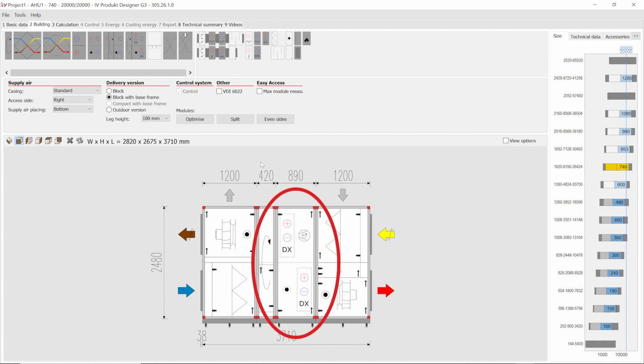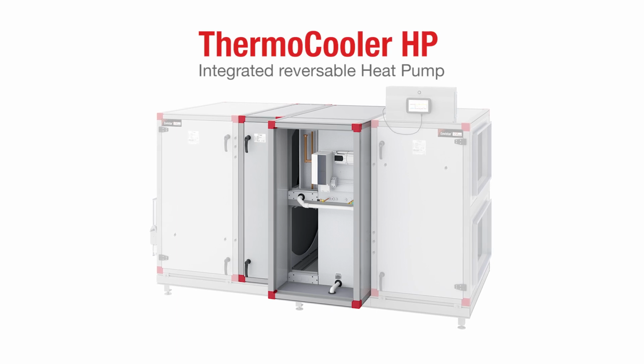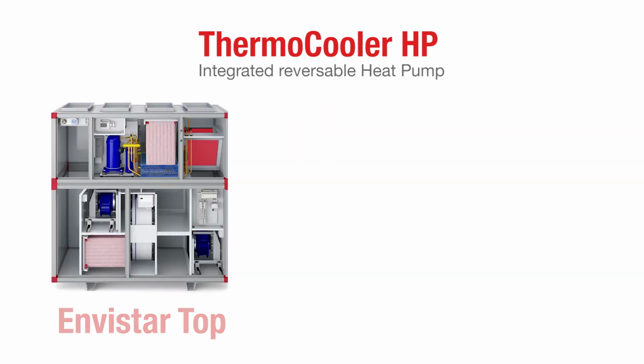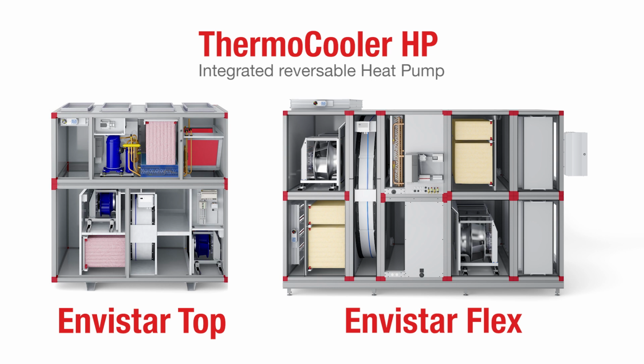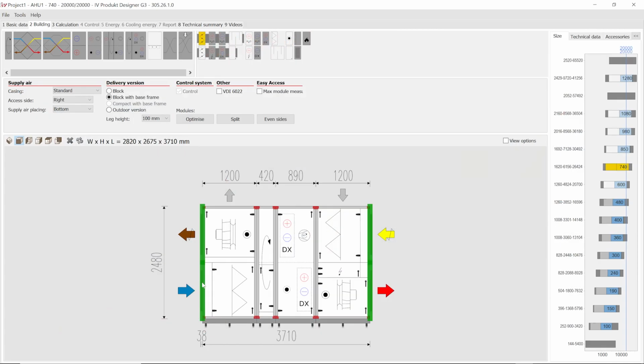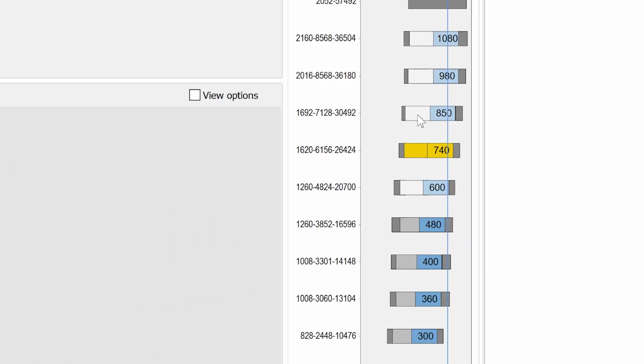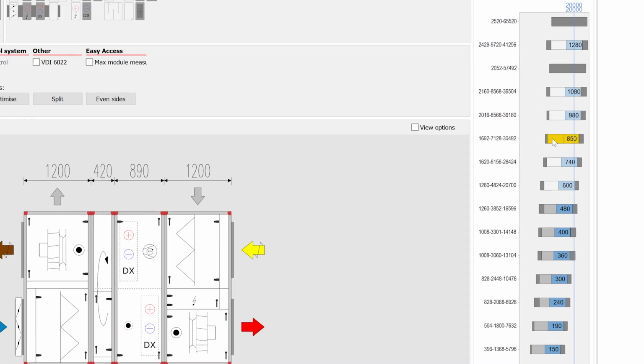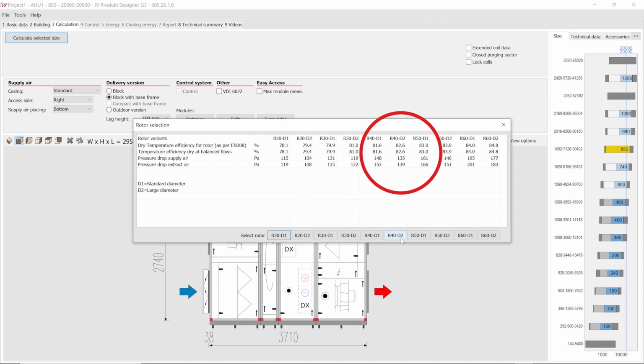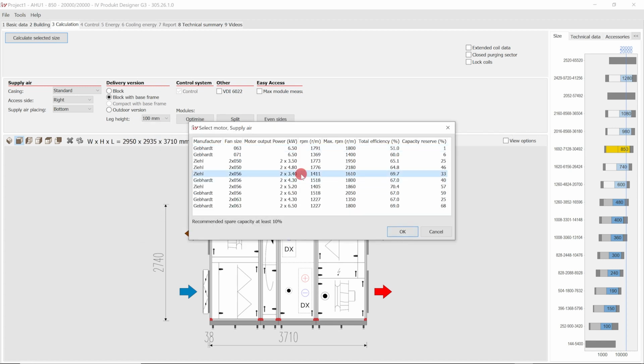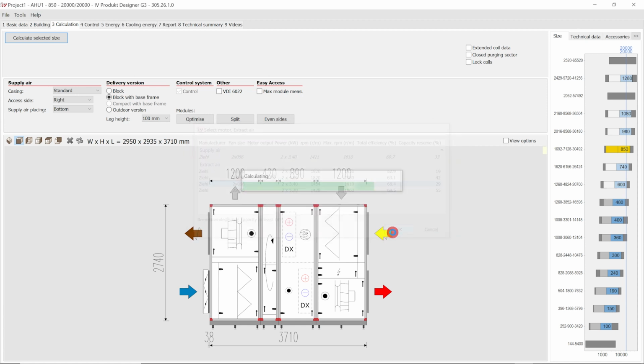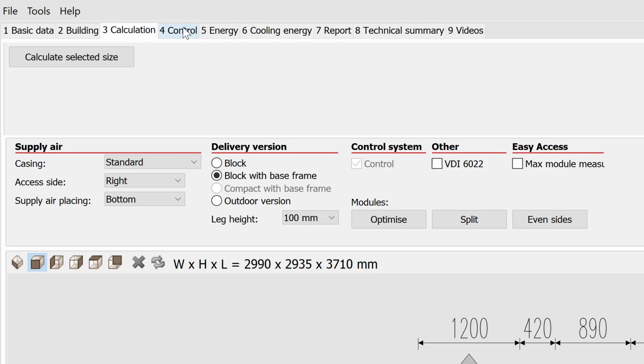The cooling unit will also be replaced, and we recommend that we integrate it into the air handling unit. In this case, a Thermocooler HP fits well. The reversible heat pump Thermocooler HP can be integrated into IV Products' Envistar Top and Envistar Flex units. It functions as a heat pump in the winter and a cooling unit in the summer. We will select the size that is appropriate for the duty. We select a rotary heat exchanger with a temperature efficiency of 82.6%. The SFP value for the fans is 1.63. Okay, the calculation of the unit is ready and standard controls have been selected.